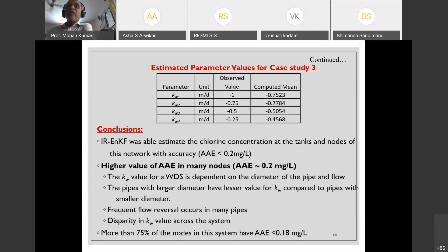Of course, similar things are also discussed here. The disparity in KW values across the system: we found that frequent flow reversal occurs in many pipes. In a network, it's possible. Then the type of reactions can also change. KW values for WDS depend on the diameter of the pipe and the flow. The pipes with larger diameter have lesser K value, KW value. Frequent flow reversal is also possible.